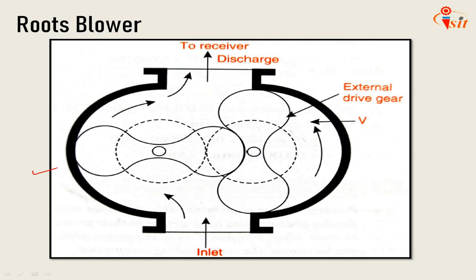One of the rotors is connected to the drive and the second rotor is gear driven from the first. In this way, the rotors rotate in phase and the profile of the lobes is of cycloidal or involute form, giving correct meshing of the lobes to seal the delivery side from the inlet side.